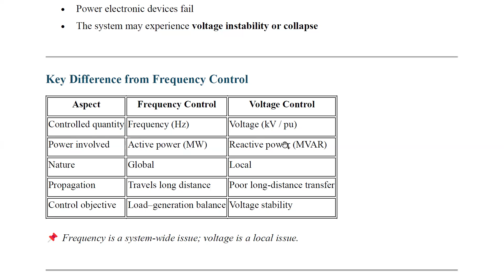So next, frequency is a system-wide issue, but voltage is a local issue. Frequency is whole system, but voltage is a local issue in that particular distribution station. Distribution system like that is a local issue, but frequency is a system-wide issue. If frequency spoils, then the whole system collapses. But if the voltage spoils, here the reactive power control is what we need to do.